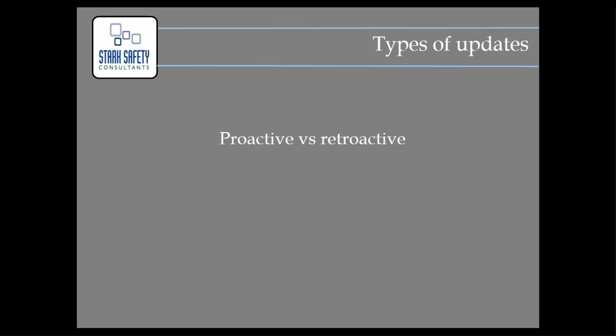Just to summarize again, the type of updates that could happen: proactive versus retroactive. Simply put, if you can take the information on a design change before you physically install it and put it into the EasyPower model, it's going to be a lot easier to validate and verify if there are any concerns with it before you physically put it in. Once it's in, now it's retroactive, and if you find a problem, the only way to correct it is to physically make that correction, and now you don't have the opportunity to possibly just do a simple model change and design change.